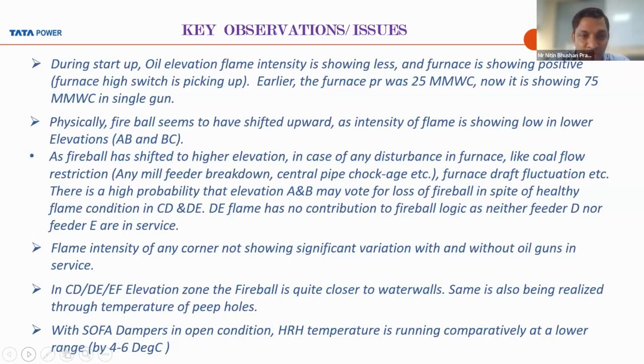As the fireball has shifted to the higher elevation, in case of any disturbance, any furnace draft fluctuation creates a high probability that the elevation A&B may vote for the loss of fireball, in spite of healthy flame conditions in C and D. D flame has no contribution to the fireball logic, as neither elevation D nor E is in service. Flame intensity of any corner does not show significant variation with and without oil guns in service.